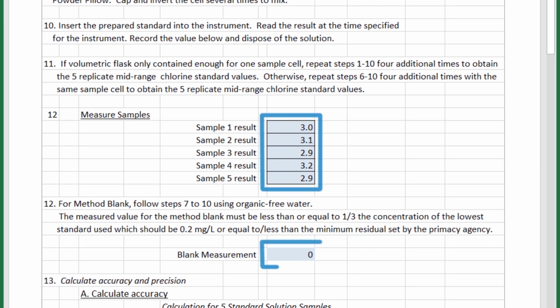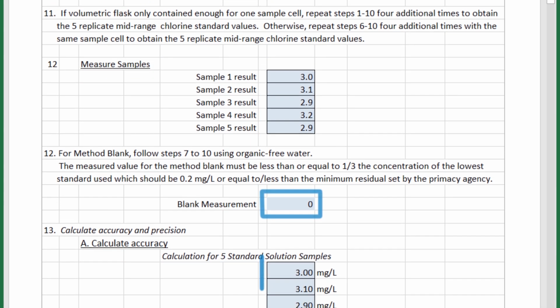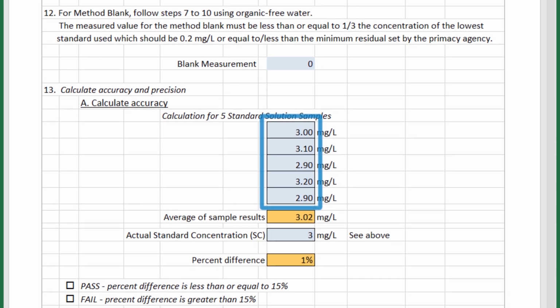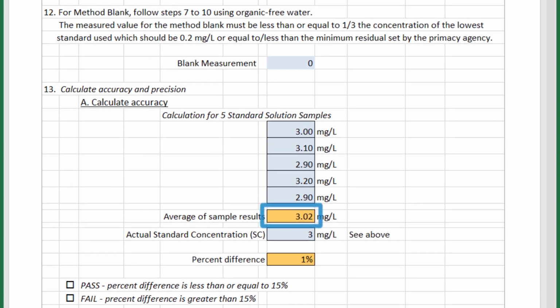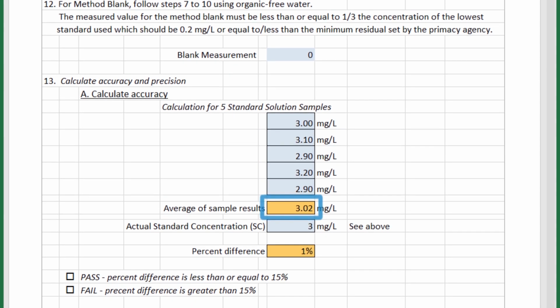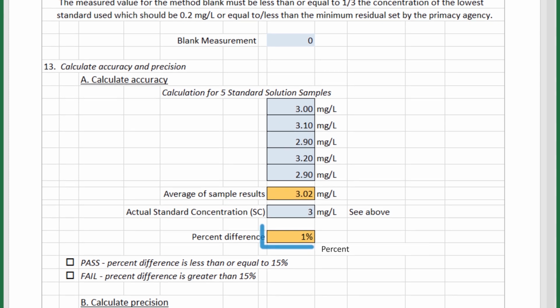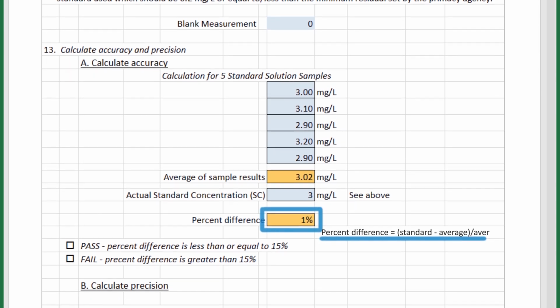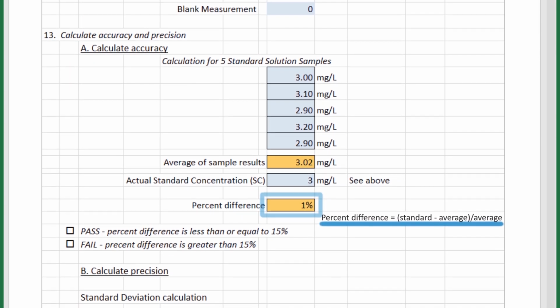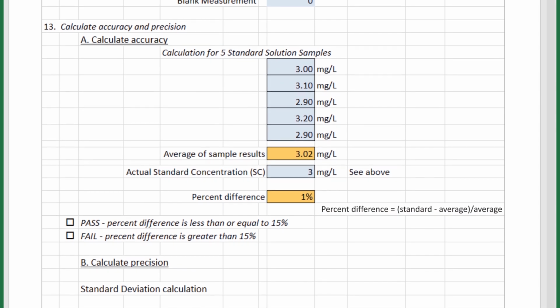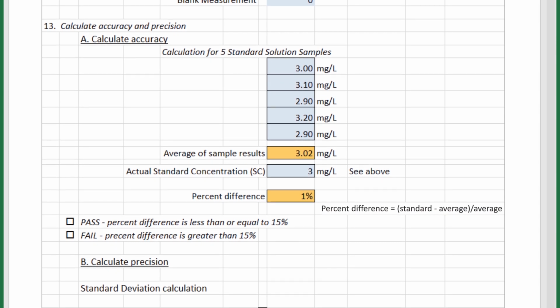Using the example on the screen, we calculate adjusted chlorine by subtracting the method blank from the chlorine concentration. We calculate the average of the 5 replicate values of adjusted chlorine. We calculate the percent difference between the adjusted chlorine and the wanted chlorine concentration. If the result of the percent difference is less than or equal to 15%, then the accuracy of the 5 replicate standards passes the IDC.